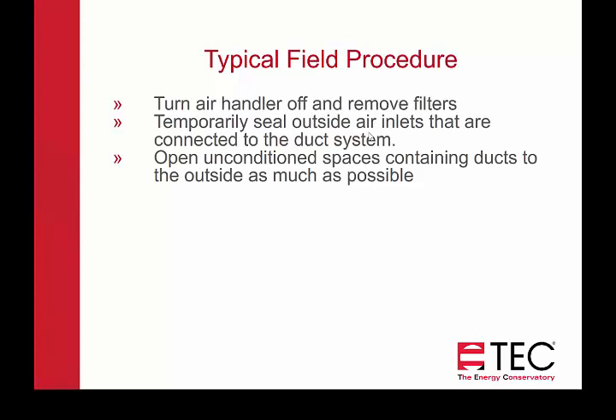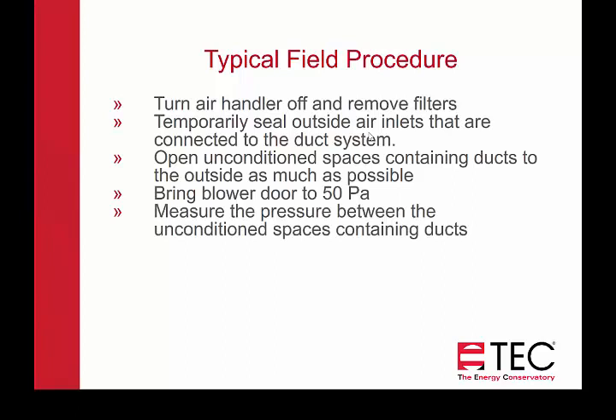The goal is to find those leaks and know the extent of them. In order to do that, you want to have the full pressure across all of those leaks so you really get an idea of how much each is leaking. Bring the blower door to 50 pascals. It's important to measure the pressure between unconditioned spaces containing ducts and the house — measure the pressure in the attic with respect to the house to see if that's at 50 pascals, and the same with pressures to crawl spaces. You might have multiple attics that aren't interconnected with each other, so you want to measure all of those pressures containing ducts. You can't interpret the readings unless you know what that pressure is. If the pressure is less than 45 pascals, it's going to be very difficult to interpret the numbers — that's an important part of interpreting your numbers and comparing readings from one house to another.